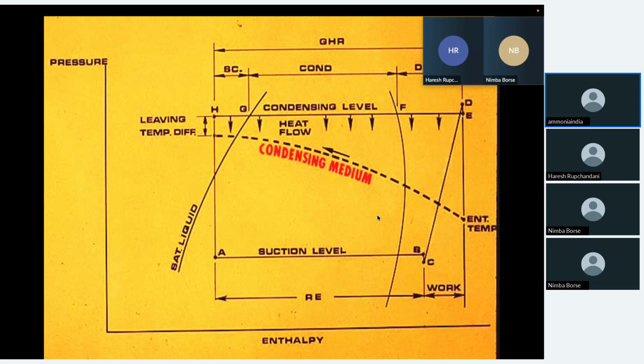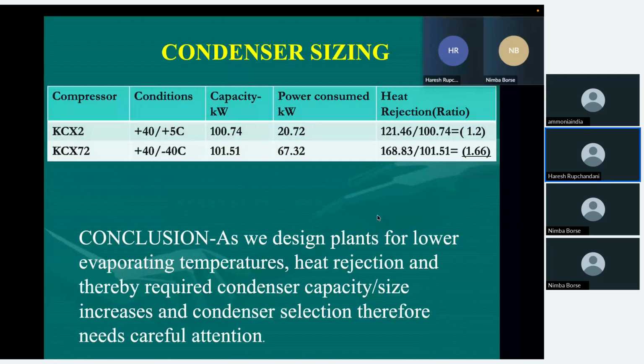Refrigeration effect plus work done by the compressor is the total heat rejection in the condenser. For example, a compressor working at 40 degrees plus 5 degrees has a capacity of 100.74, and the power consumption is 20.72. So the condenser should be designed for 121.46. That is the addition of both these two. So the ratio is 1.2.